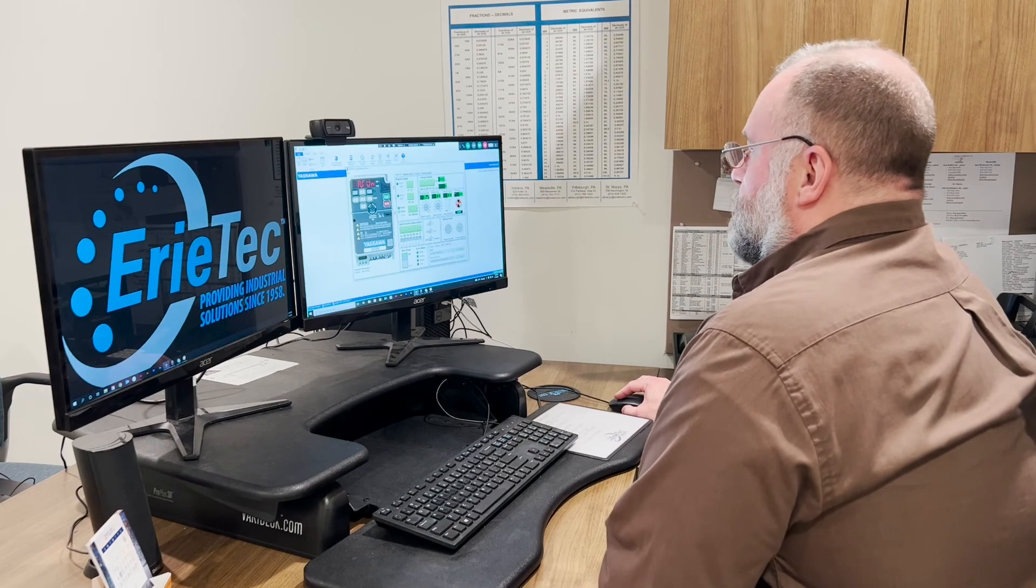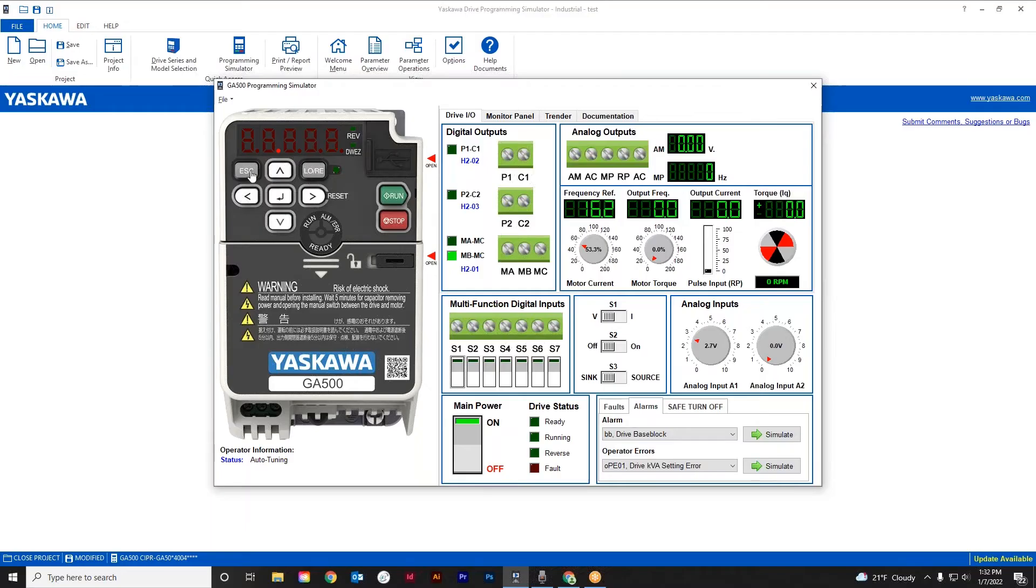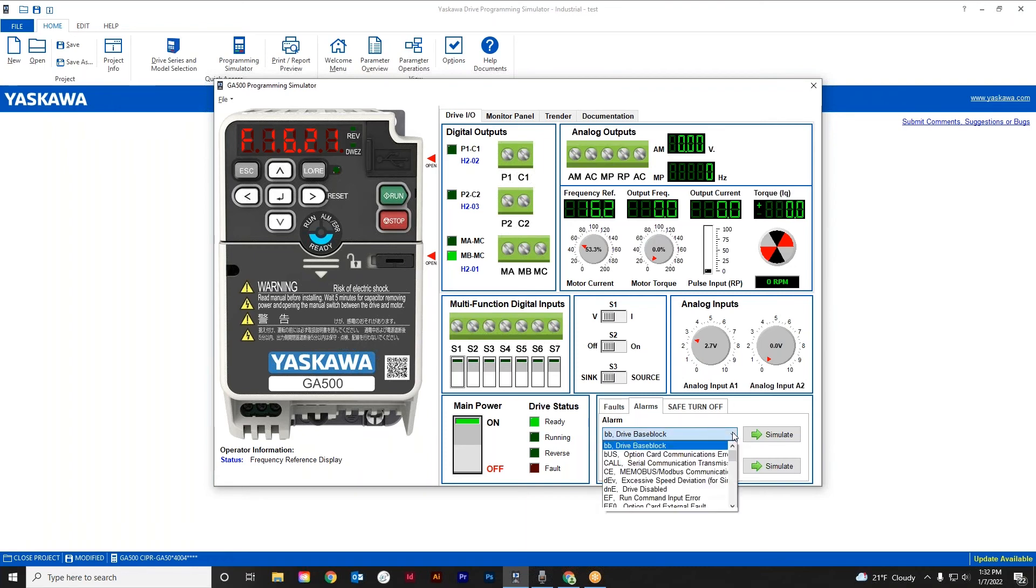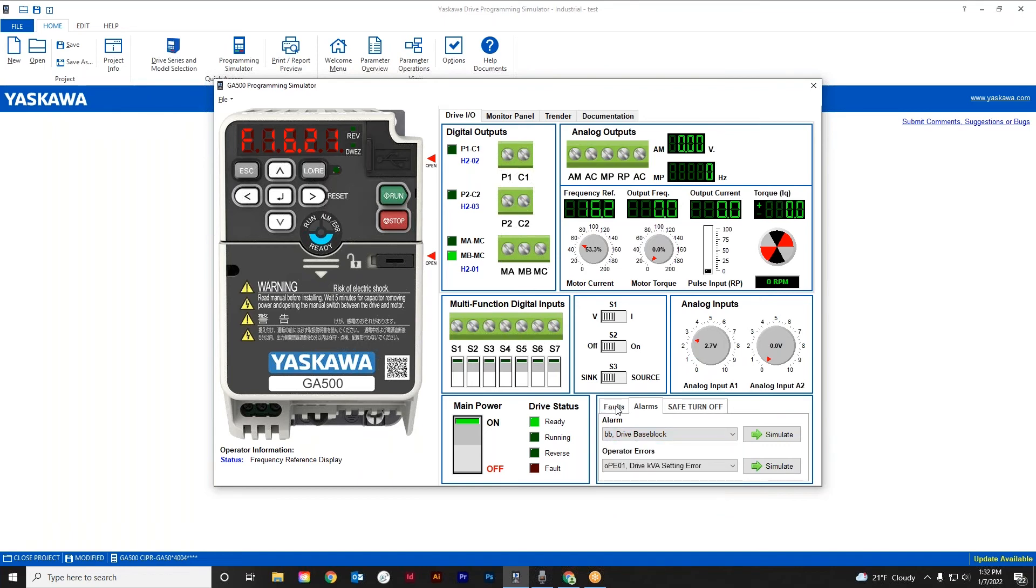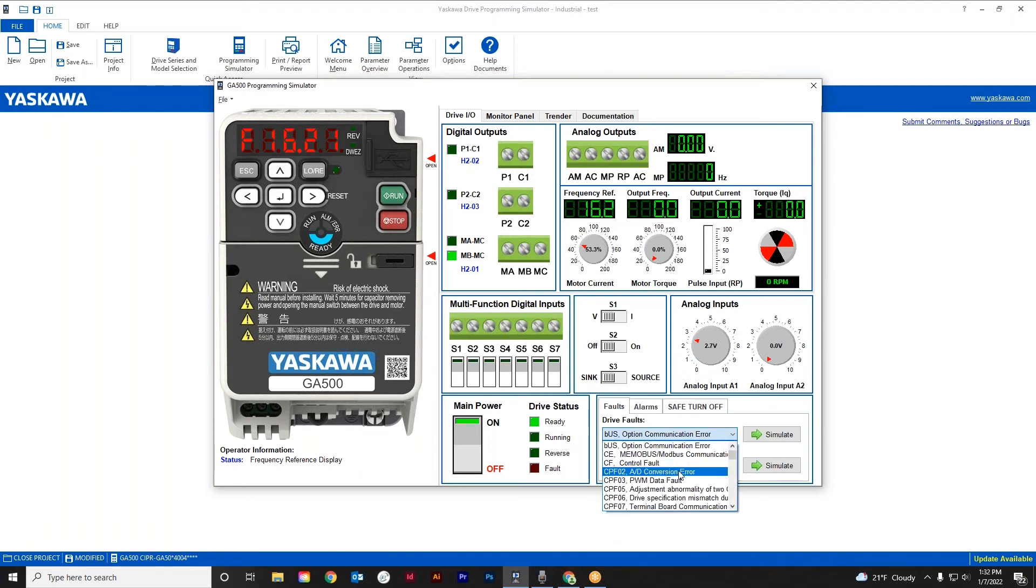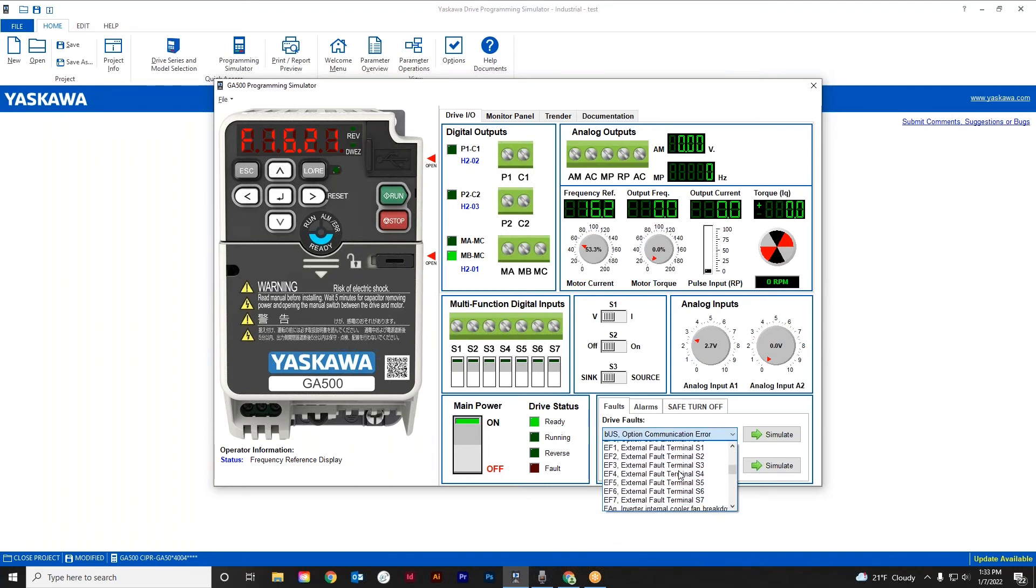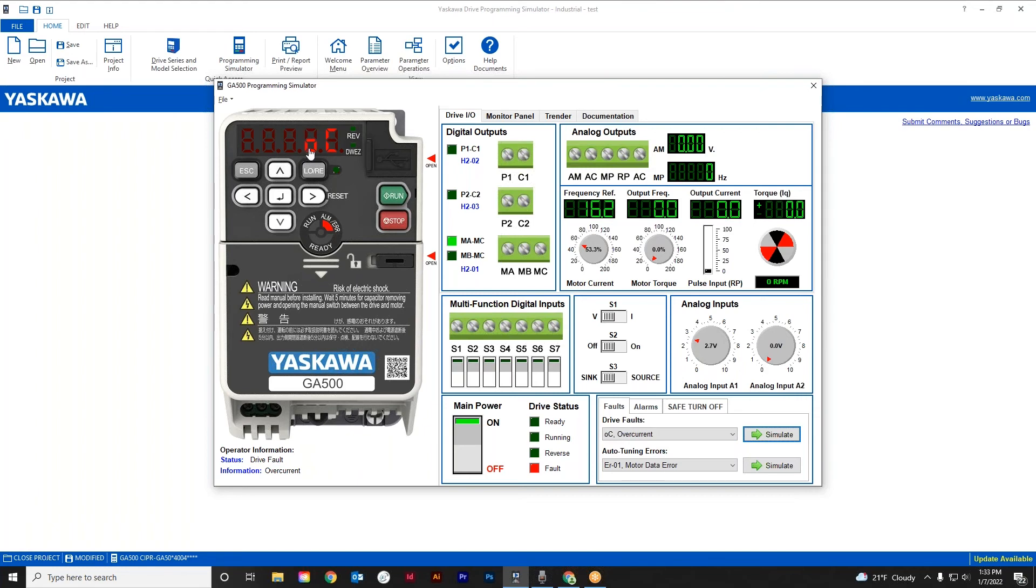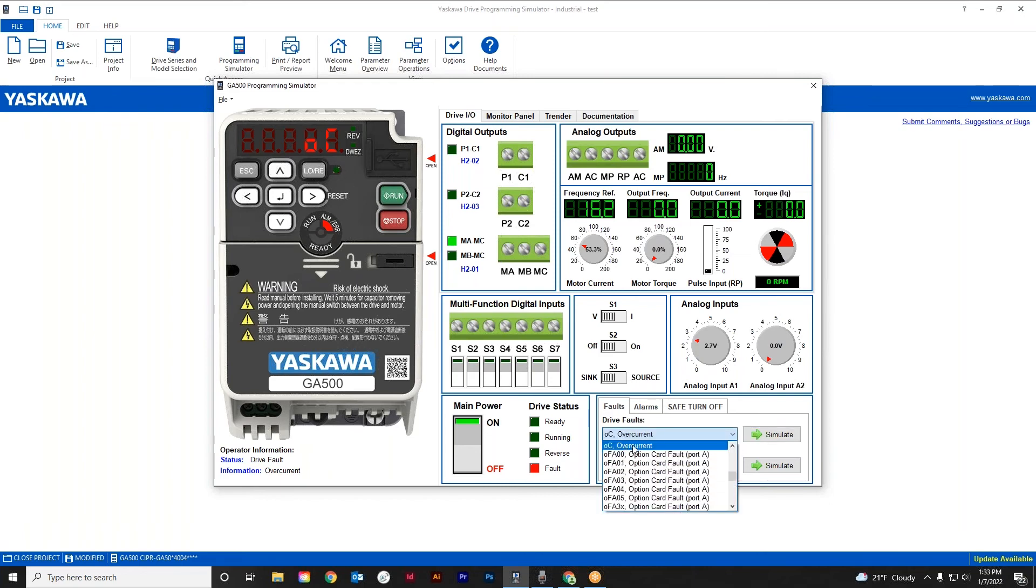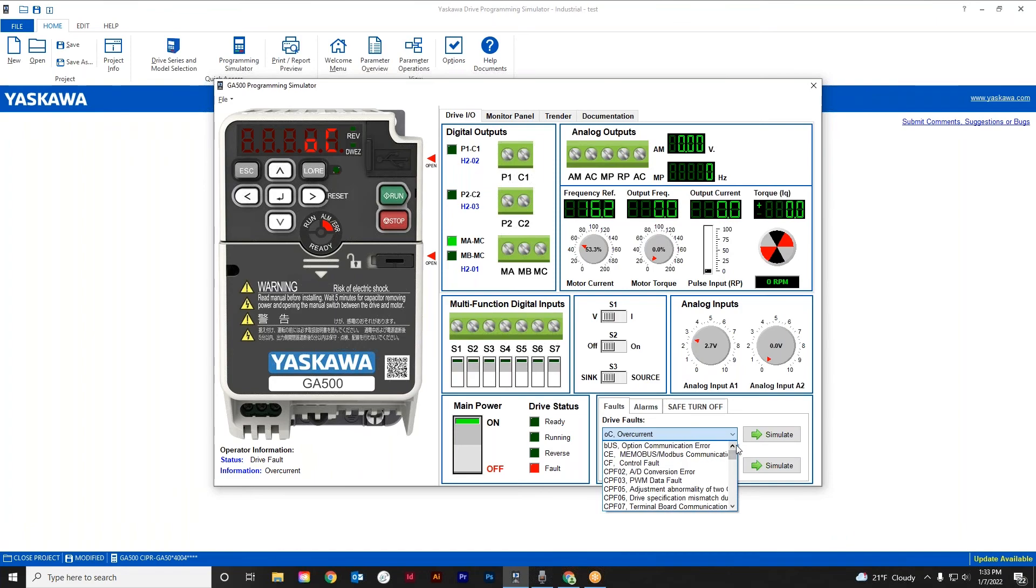And if you'd like to see what various faults are, let me get back here to the main screen. If you want to see what an overcurrent actually looks like, I can scroll down here and over here on this bottom right hand side, I went from faults to alarms. I'm actually can create a fault. So let me give an overcurrent fault for the heck of it. And you'll see what it actually will look like on the display. That's kind of neat. Again, what are you seeing in the field? We can simulate it here. Sometimes the Yaskawa speak at little O's and big C's. What exactly does that mean? There could be other funky nomenclature in here. Like, I don't understand it. Well, again, we can simulate that here. So you can actually see what it means in real world, which is kind of nice.